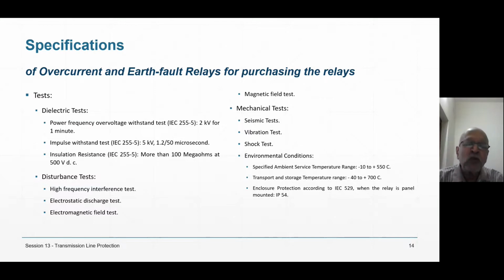It's quite possible that you may say that I will see only these certificates. That's all. But you say that no, I want to witness the test. So what are the tests? Power frequency over voltage test. All live contacts of the relay are shorted together and earthed, with one earthing terminal. Between them, 2 kV is given for 1 minute. The relay should not be damaged.